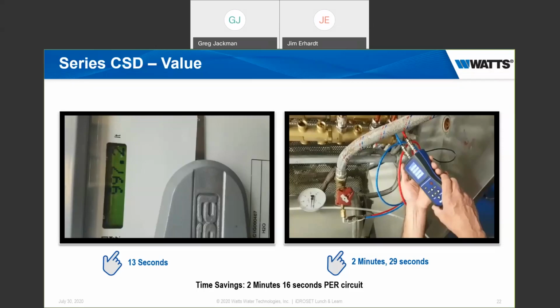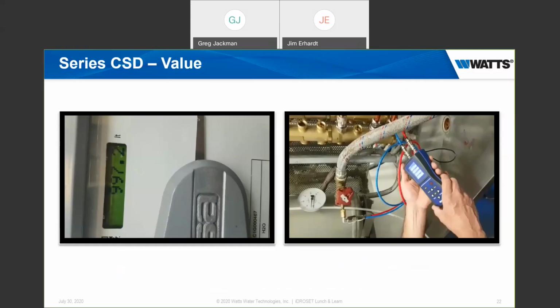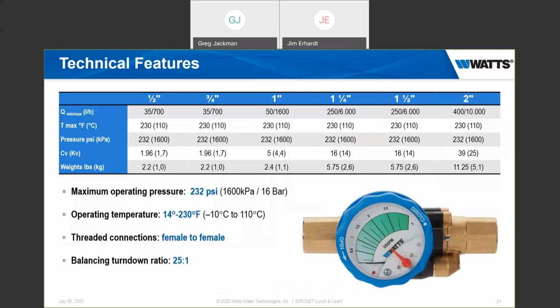Okay, I'm just going to read off 2 more questions here, then I want to move on. Does the iDROSET include some sort of handle locking mechanism? Yes, that's the nut that we saw on the previous slide. See if I can go back to it. Right there. If you look at the iDROSET in the bottom right corner, you'll see that stainless steel Allen key screw at the 3 o'clock position coming in from the side. So once the valve is set, screwing that screw in locks the handle so that it cannot move inadvertently.